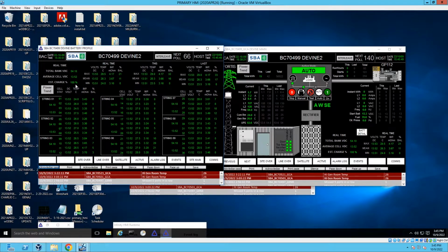In real time, we have our max, min, and mean values on a cell-by-cell basis for DC voltage, temperature, internal impedance, as well as balance, as a percentage of current bypassing capacity. In the lower portion of the page, we have access to real-time data on each individual cell in the bank. These are 12-volt cells tied together in series to make 9 independent 48-volt strings.